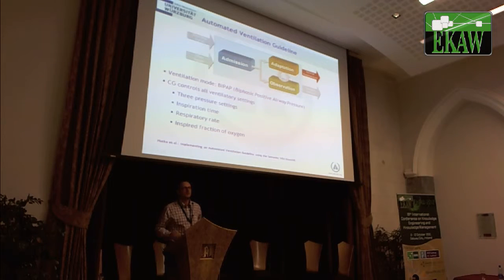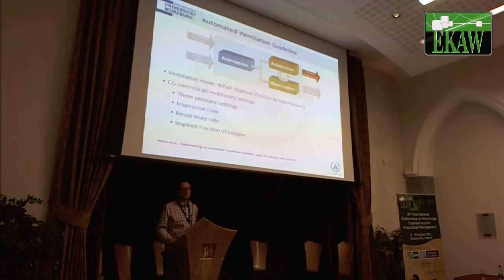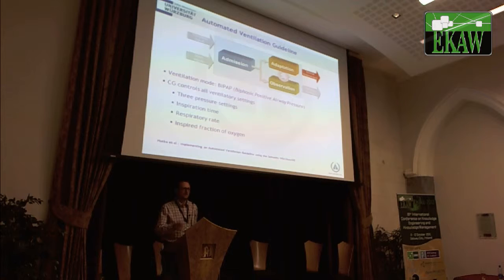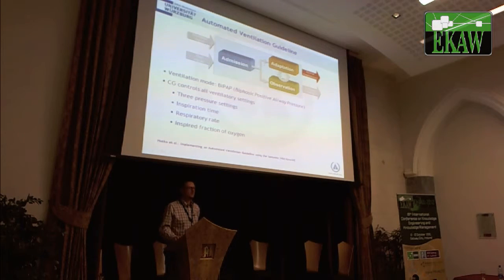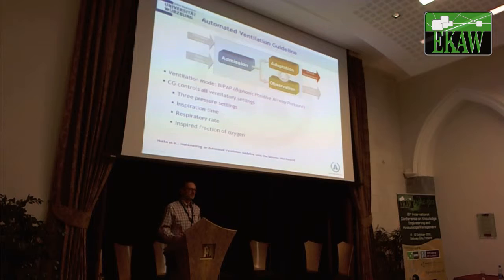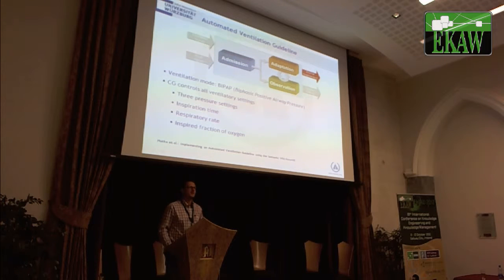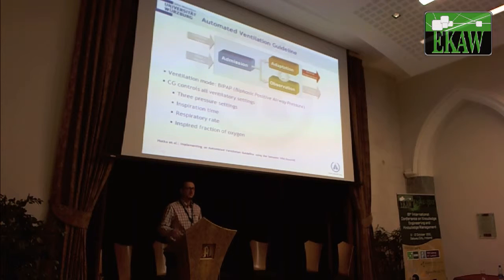Here's an overview of the ventilation guideline. It's a guideline for one specific ventilation mode called BiPAP, which stands for biphasic positive airway pressure. The guideline is able to control all six ventilatory settings available in that ventilation mode: three pressure settings, inspiration time, respiratory rate, and inspired fraction of oxygen. The picture in the upper half gives a rough idea about the structure of the guideline.